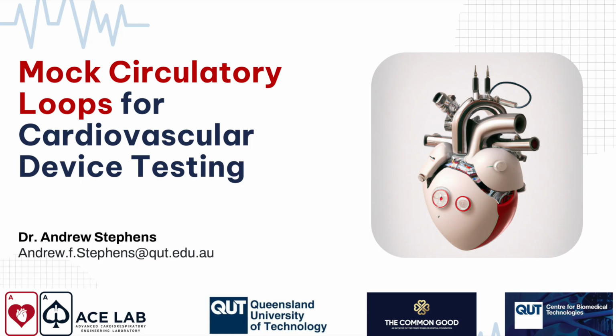So it's all very well and good to create this water displacement in our ventricle, but if we don't have valves, it's not going to flow in the right direction. So there are a couple of things to consider when picking valves. And the main one is pick a valve with a low pressure drop to avoid simulating aortic stenosis.